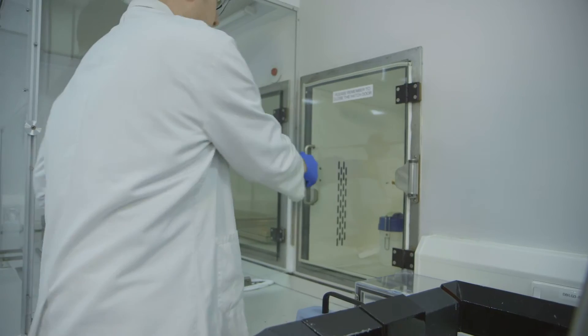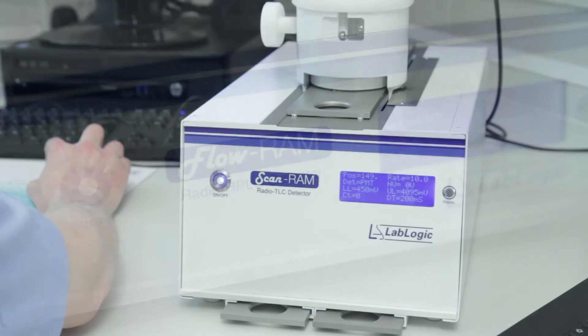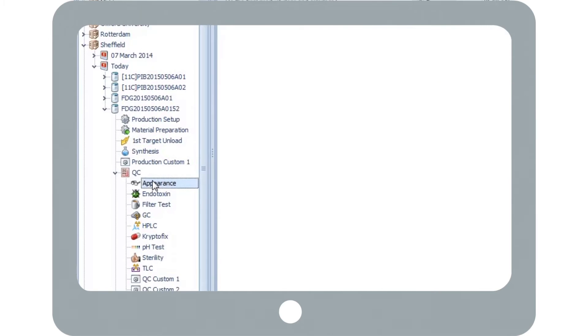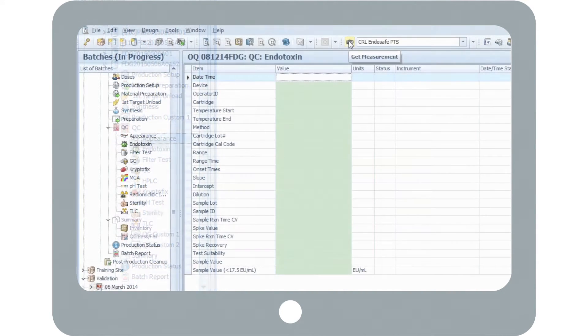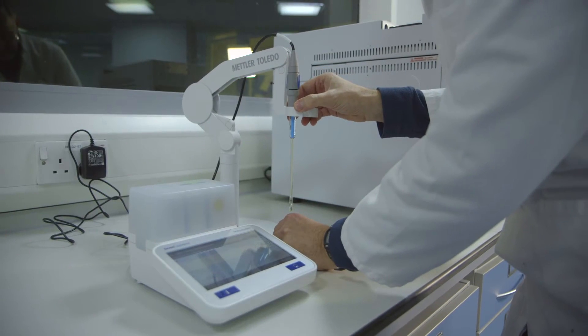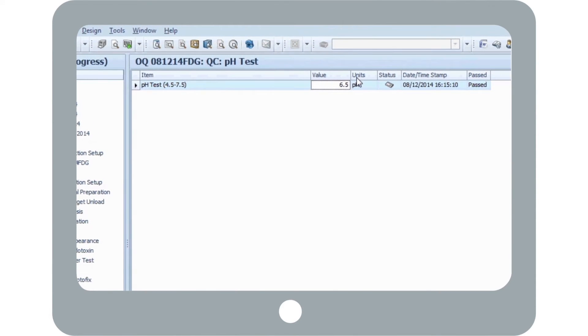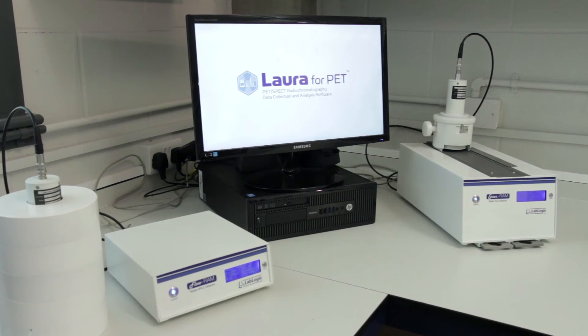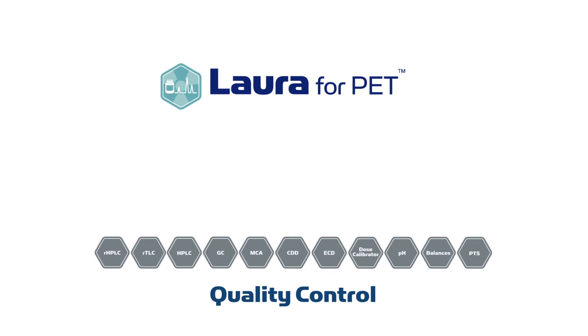Petra brings all key quality control information directly into the batch report. The system interfaces directly to each piece of equipment or its software package. As some tests are done manually, Petra allows for data entry with a full audit trail. For customers wanting to streamline the control of their radio chromatography equipment, there is a dedicated single point of control software package called Laura for PET.